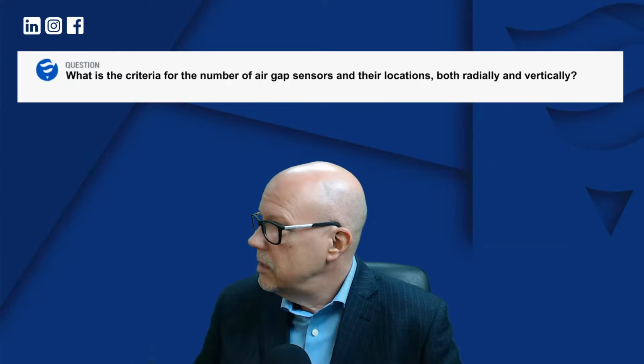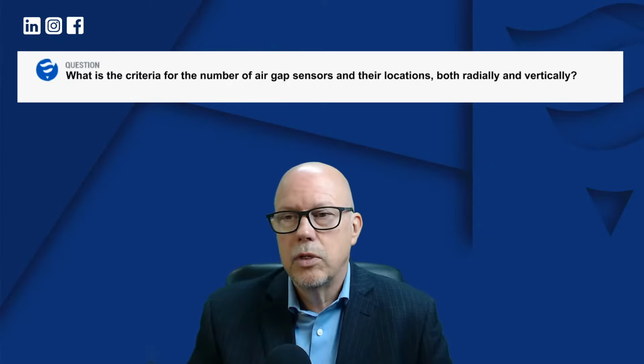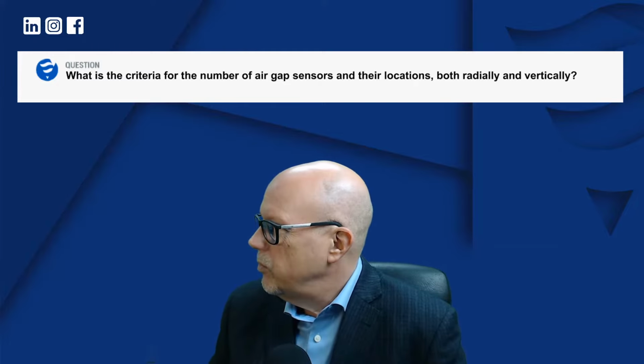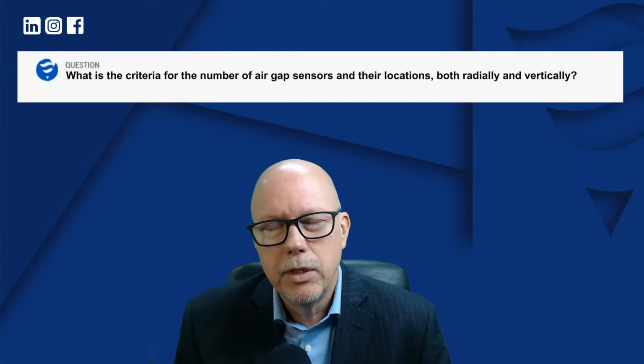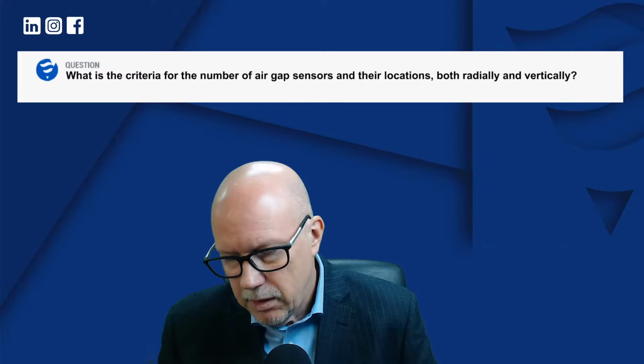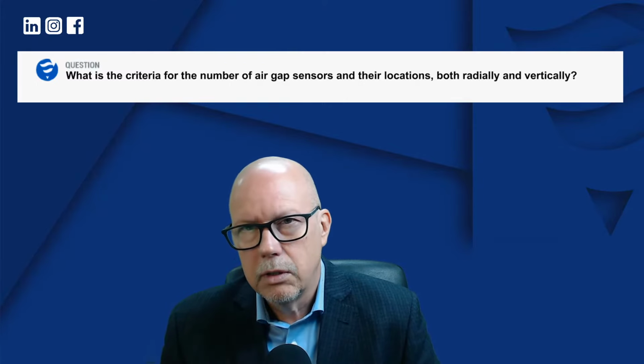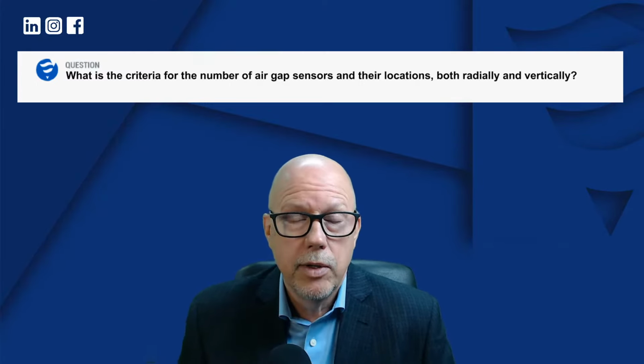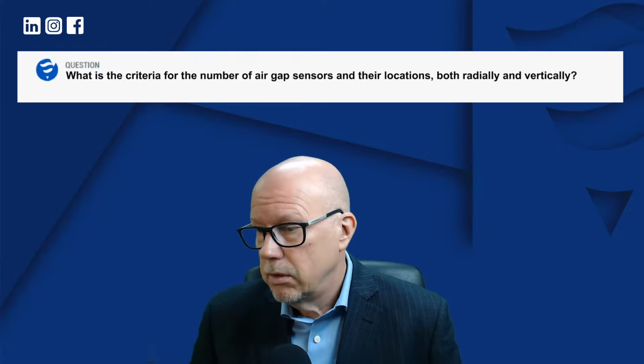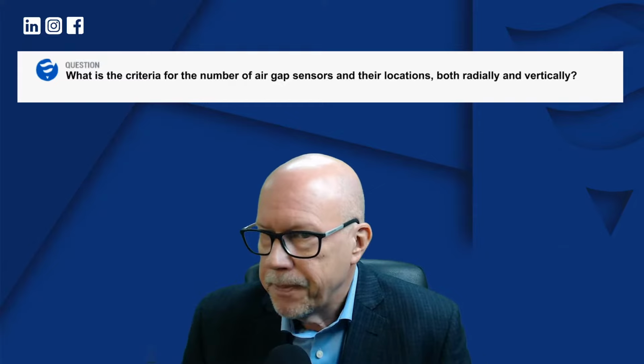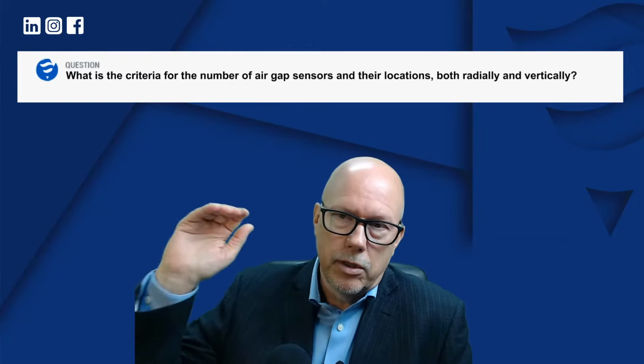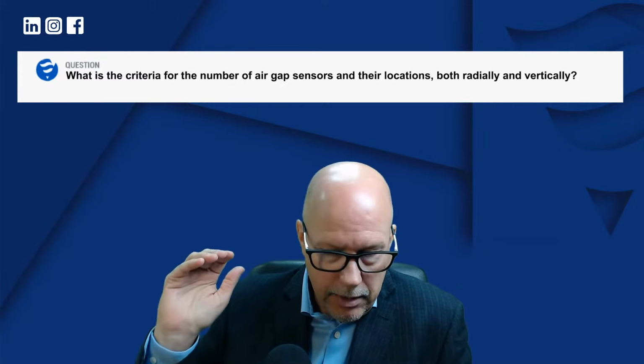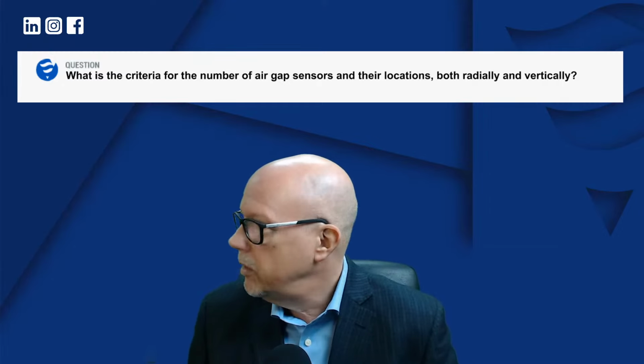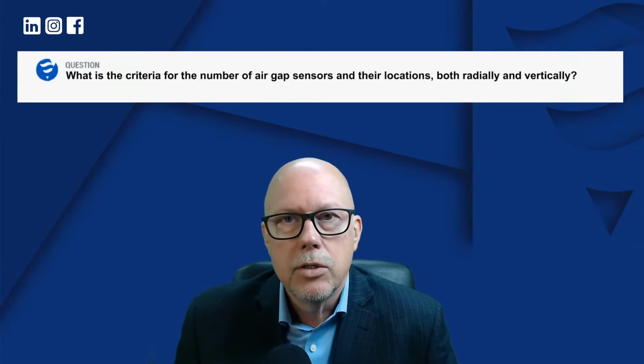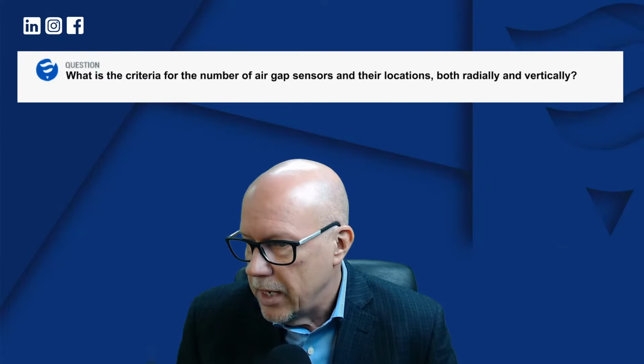And in fact, we had a case at the Itaipu power station where the rotors, I believe, were like 3.2 or 3.4 meters. And they suspected that the smallest air gap was neither at the top nor at the bottom, it was actually at the middle. They believed that the rotors would have a convex shape, and we installed sensors at the top, at the middle, and the bottom, and they were absolutely right. All the smallest air gaps were in the middle, so the rotor poles were actually sticking out.